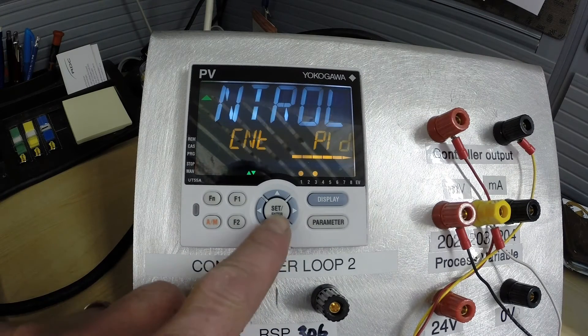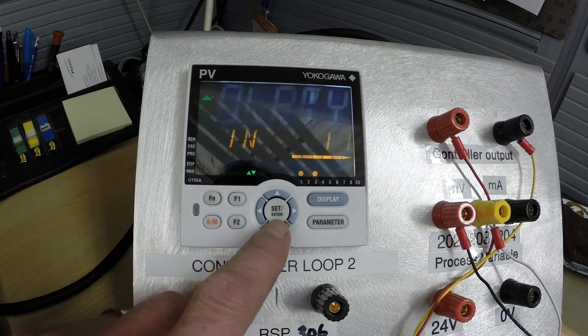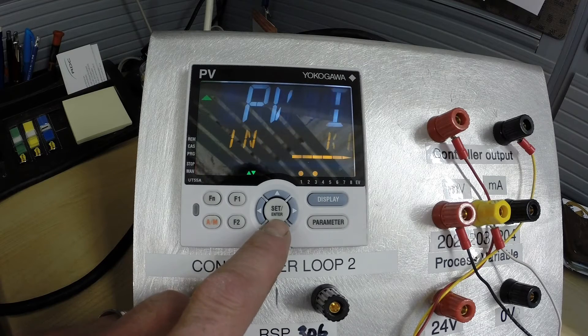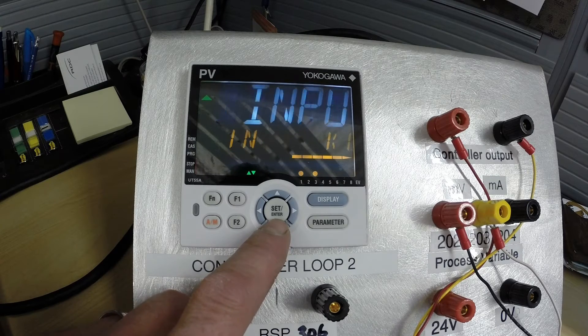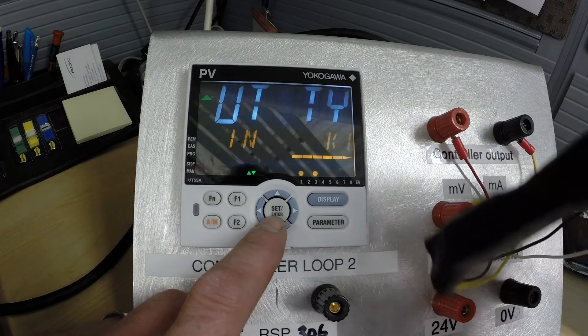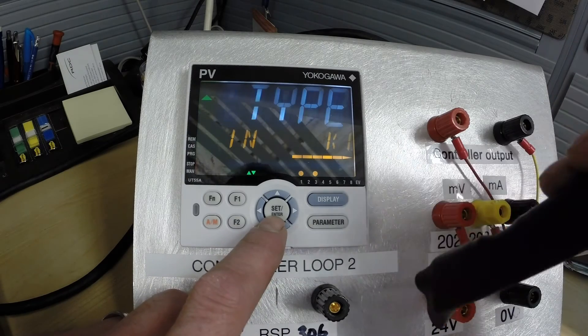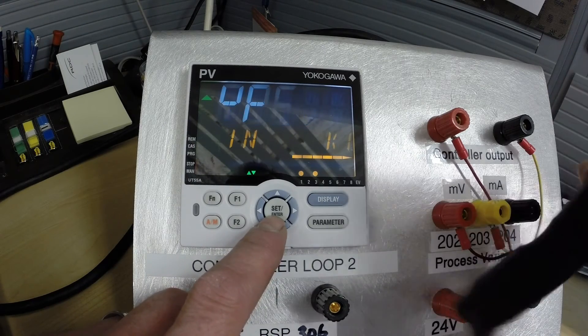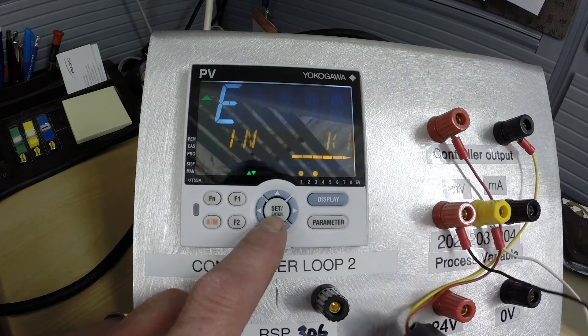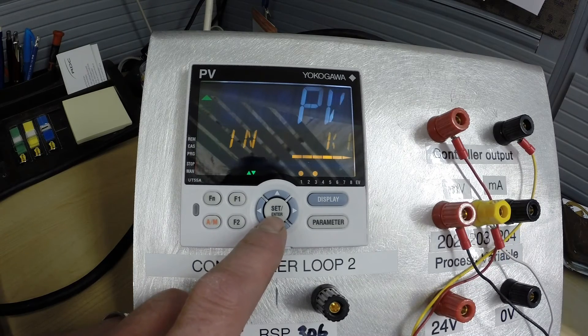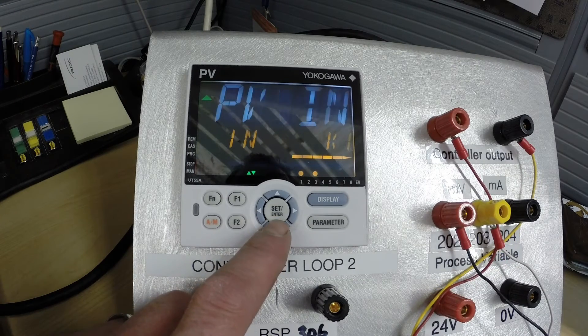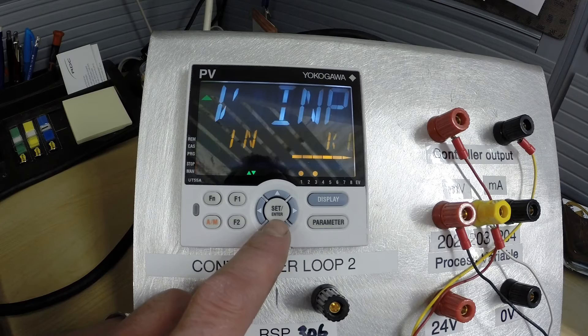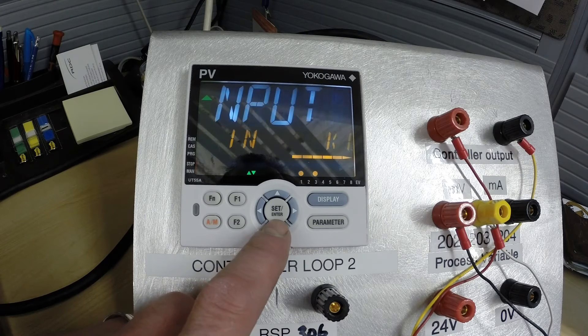Control type is PID which is what we are after. Input type in this case for this simulator is a type K thermocouple. So we're going to leave that in there. You may have to change it from 4 to 20 to K1.